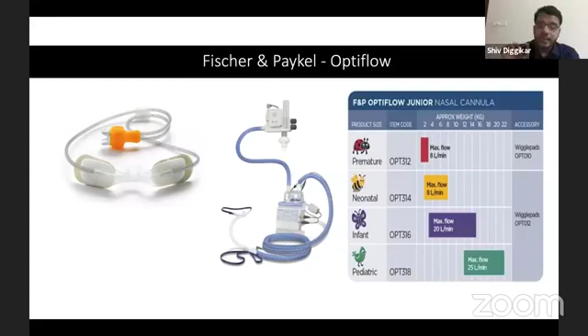Fisher and Paykel OptiFlow Junior. The set would be pretty much like a CPAP set, except that it doesn't have an expiratory limb. So you will have only the inspiratory limb in HFNC, and this is the HFNC cannula by Fisher and Paykel, called OptiFlow Junior. If you see the interface here, it is very peculiar: it is a tapered interface. It tapers and the prongs are very small and very soft. That is the advantage it has over others.